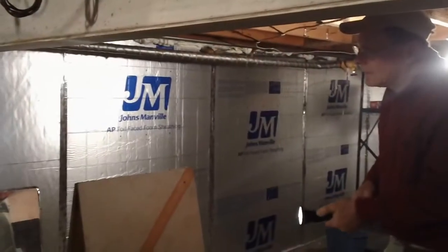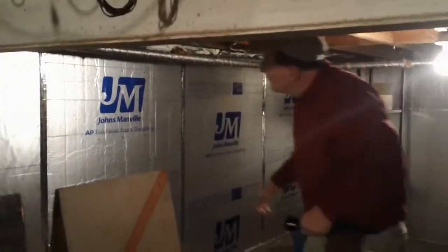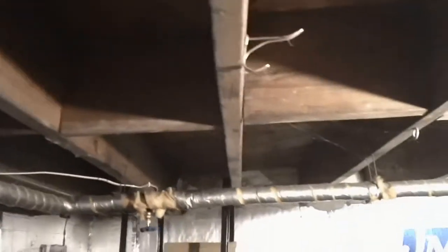Basement crawl space. As you can see, this is some foil-faced foam sheeting board that was put in to insulate the crawl space wall. Helps reduce heat loss. Also, if you look up in here, you can see expanding spray foam that was used to seal the sill box. That air seals the house and also insulates this area of the home. And this was done for the entire home perimeter. You can see where there's a small cavity there, but the larger cavities are all filled. And they're filled with fairly adequate foam to the point where it's out.